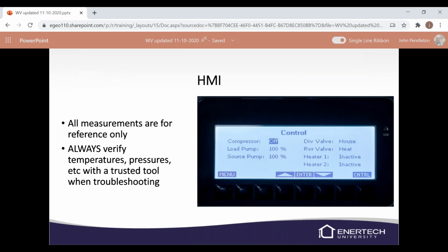So again, on the human-machine interface, all measurements are for reference only. You can verify them with your refrigerant gauges, your pressure gauges, and your thermometer, and make sure you're always installing pressure temperature ports in the system. We still need those pressure temperature ports on the load and on the source. And if you've got a buffer tank or a hydraulic separator, I would install pressure temperature ports on the zone piping near your pumps for your external pump as well.